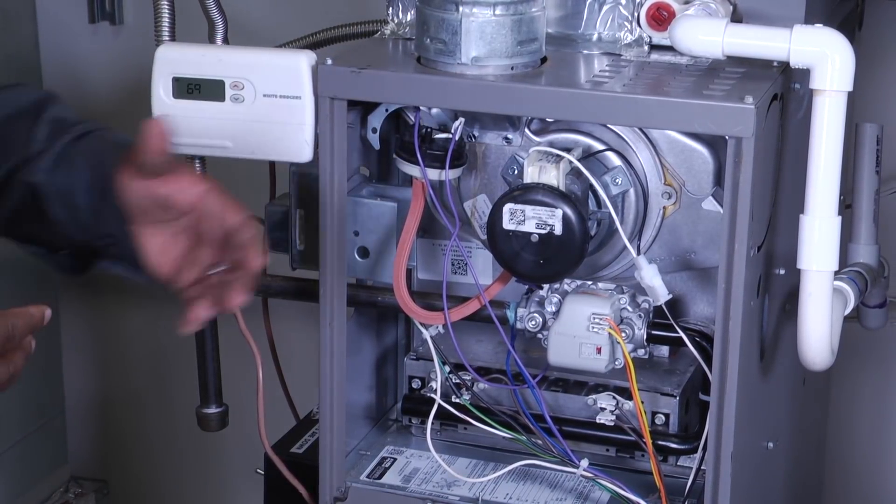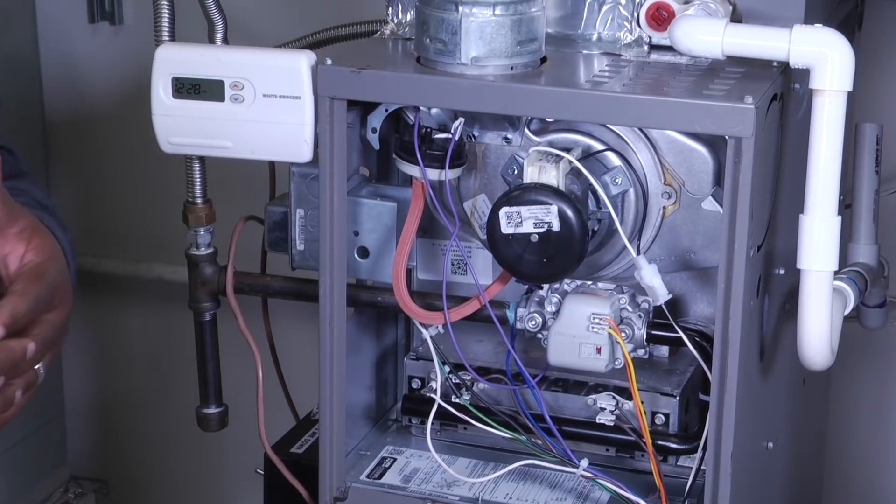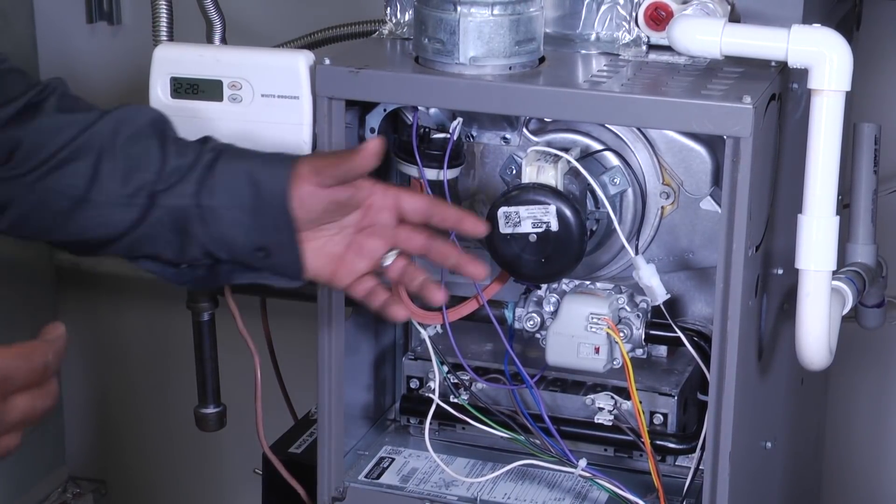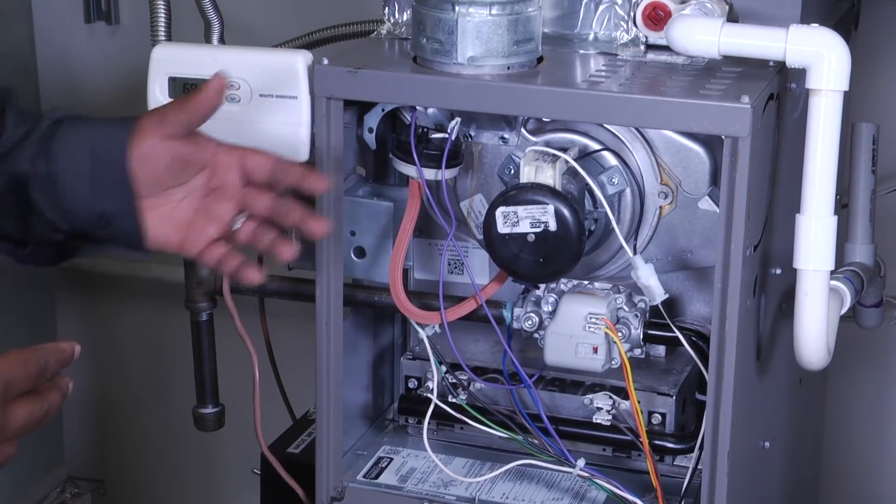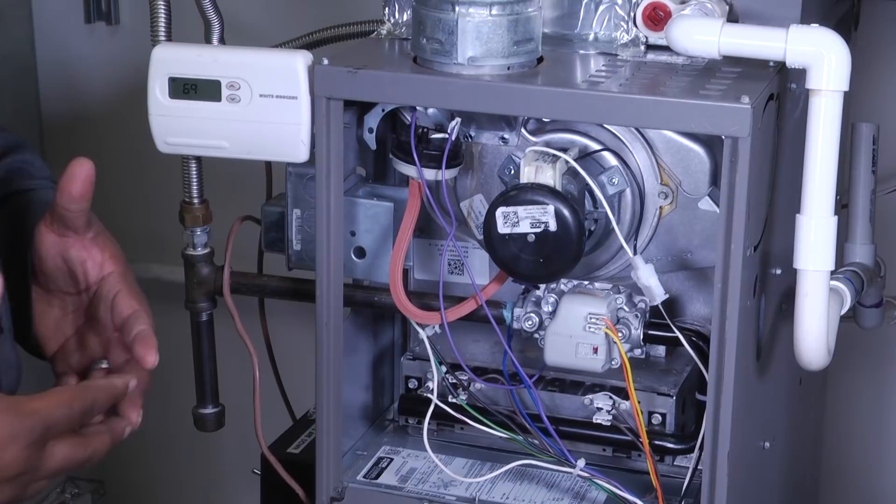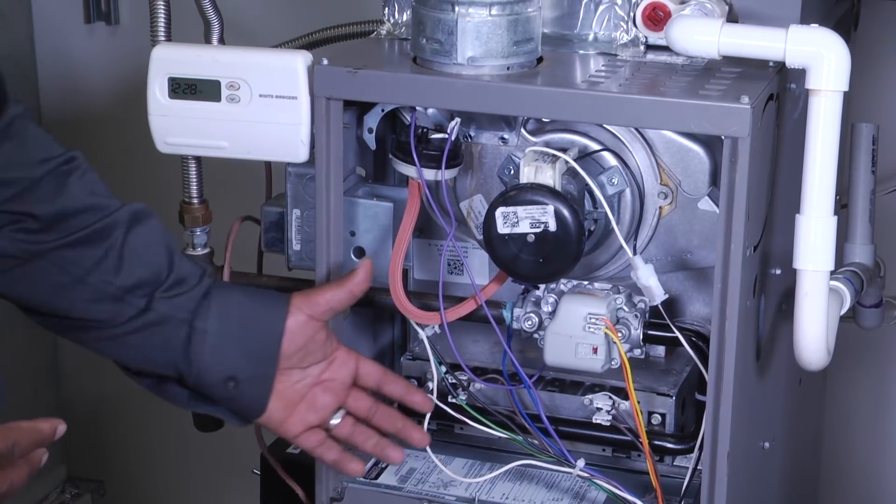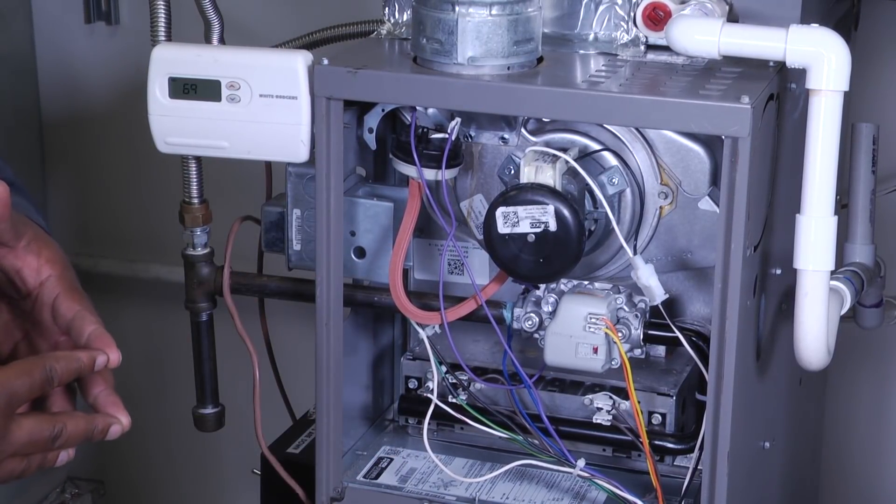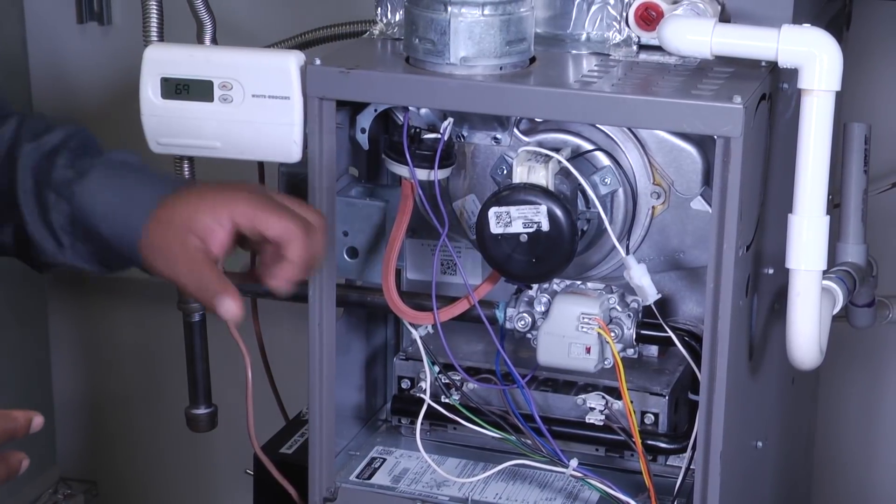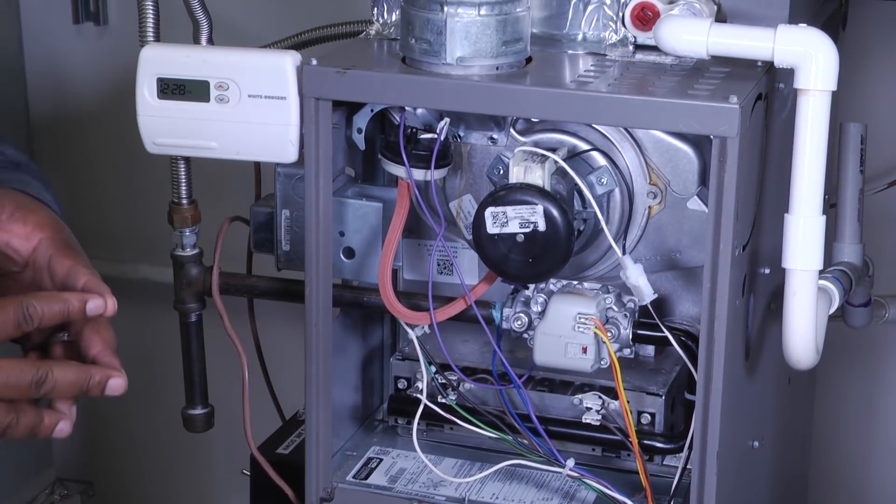The next thing that'll happen is our inducer draft motor will begin to spin to cause a draft. Shortly after, the inducer draft motor pressure switch is going to prove that our inducer fan motor is working. Shortly after that, we'll see a glow from our hot surface igniter. After that, the gas valve will open and then we'll hear that foosh and get that flame.